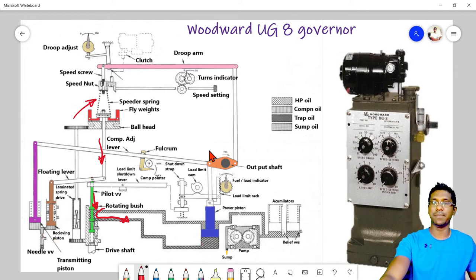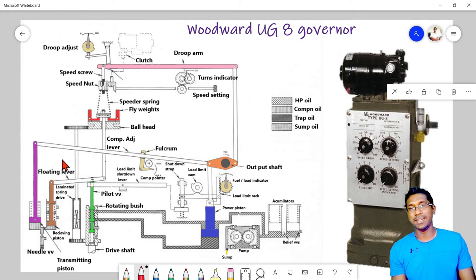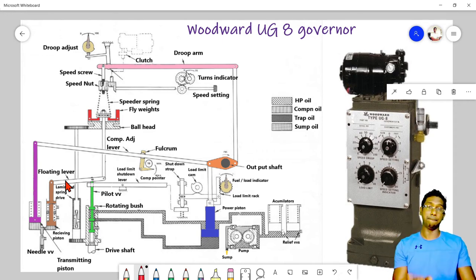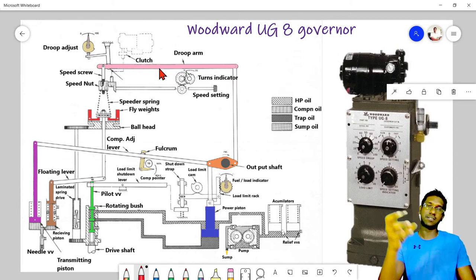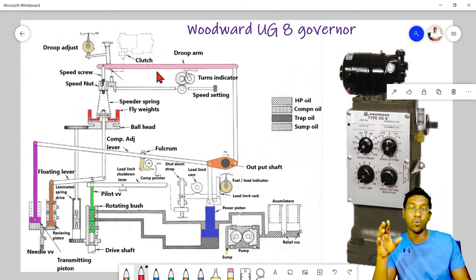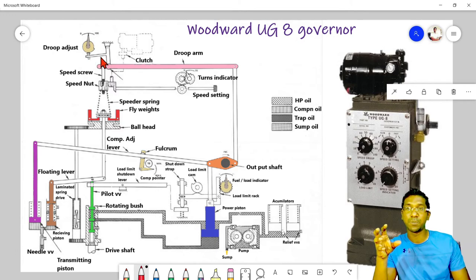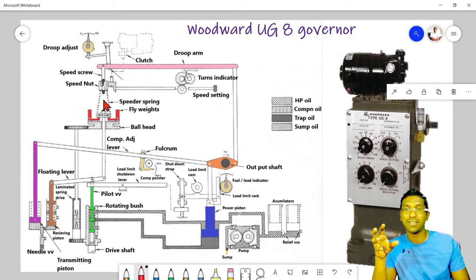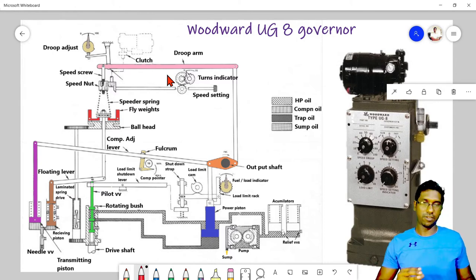The output shaft is connected to the droop arm. In the compensation system we have a transient droop — a temporary droop — but the main droop arm provides permanent droop characteristic needed for parallel operation. The droop adjusting lever has a cam arrangement where the pivoting point can slide, changing the mechanical lever advantage acting on the spring. This changes the negative feedback and proportional action, hence the gain, varying the offset value.